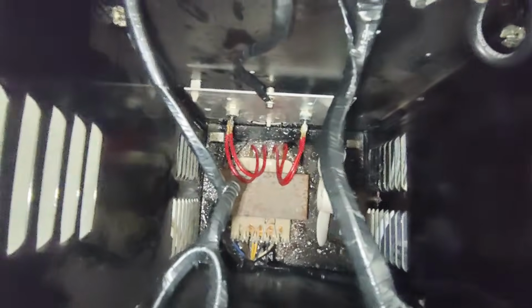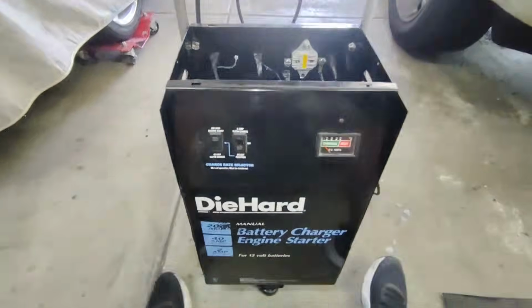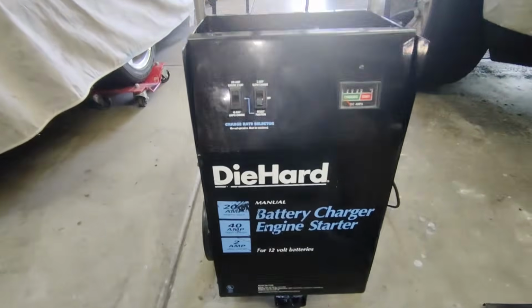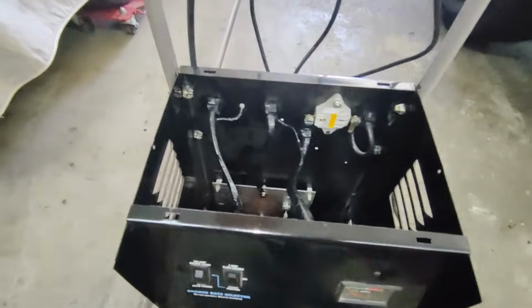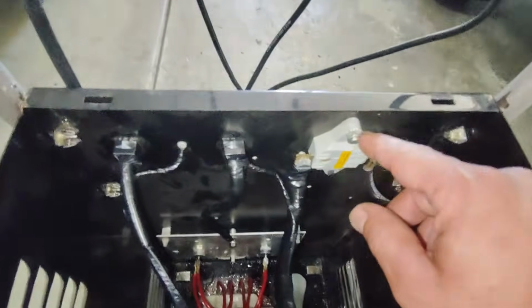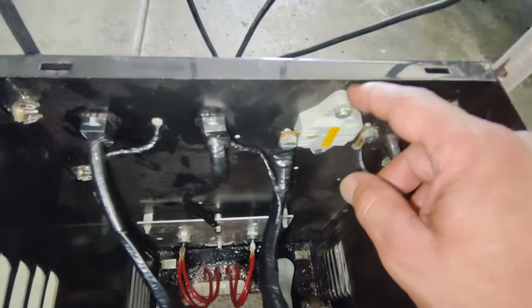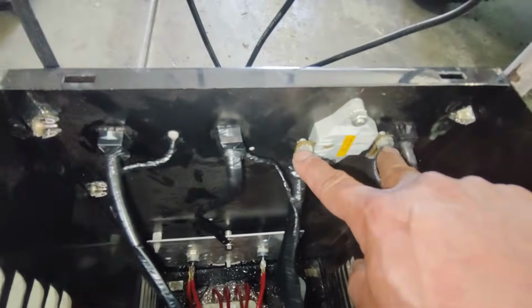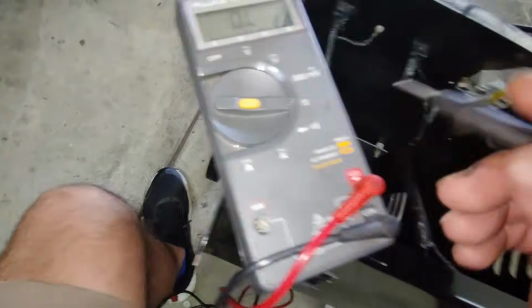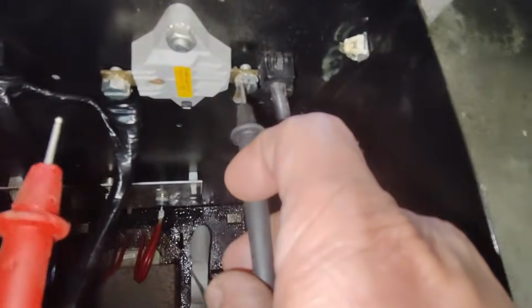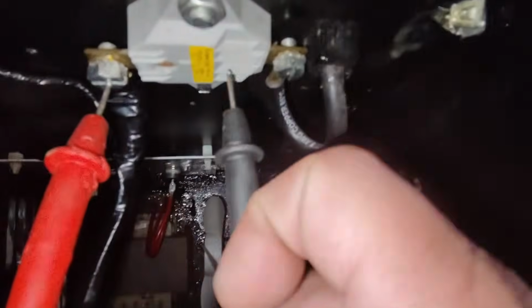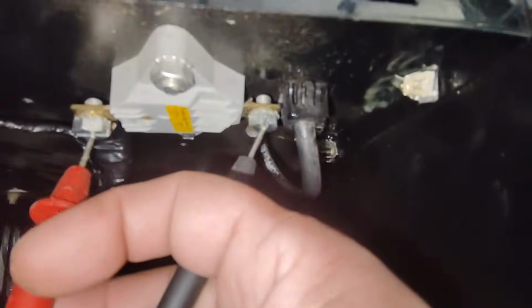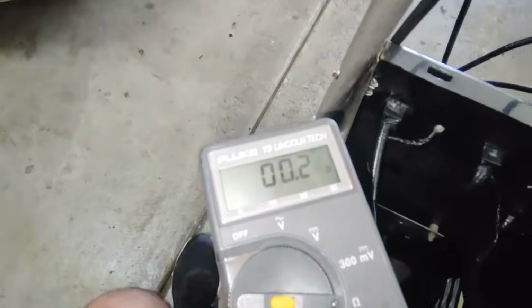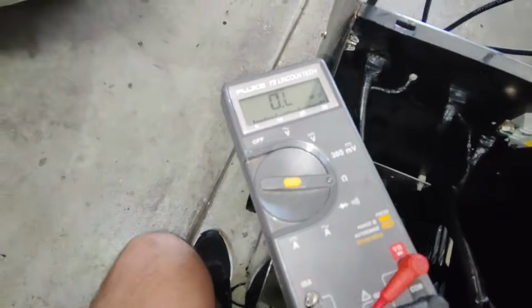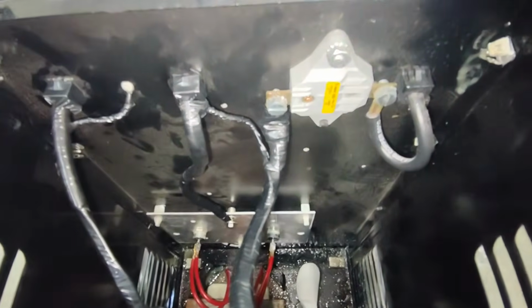The transformer inside of these is a pretty robust transformer. Many other brands are going to be quite the same as far as how they are internally. Now a common piece that I've replaced on this before is this fuse or circuit breaker here. We'll go ahead and test that. With your multimeter on ohms, you can test the resistance by probing this side and this side. It tells me at least it's not open. Circuit breaker's okay, again that's a common failure part. Sometimes those do go out.